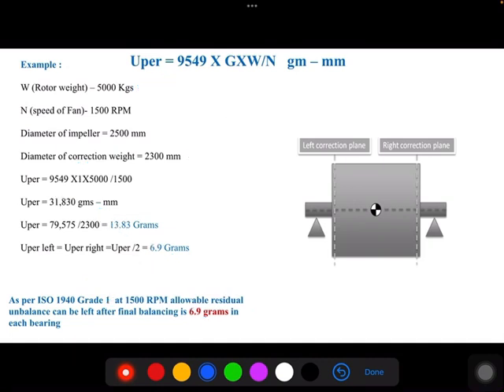So if you go for the lower grade, again OEM has done the balancing by applying the balancing grade G1. So in place of this formula, you put here G as 1. Remaining all the parameters are same. The weight, impeller diameter, RPM are same. Then you get 31,830 gram-mm, then you need to divide by this 2300, then 13.83 grams per bearing, that is 6.9 grams. Means as per this standard, if you use the grade 1, then 6.9 grams is the allowable residual unbalance left after balancing.